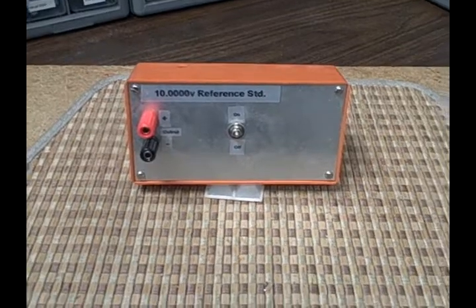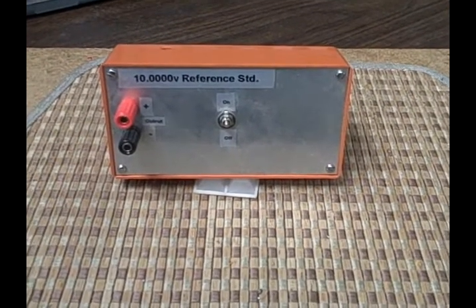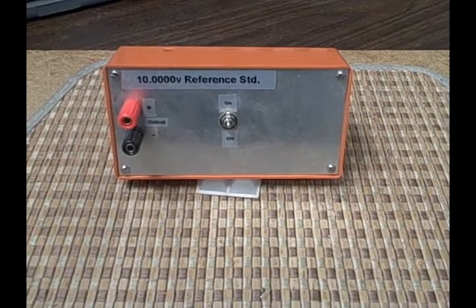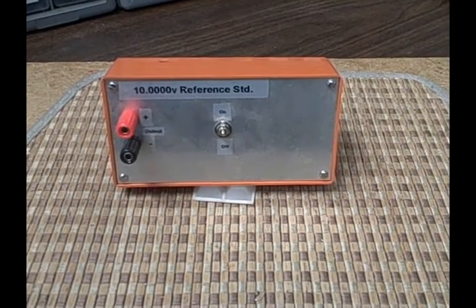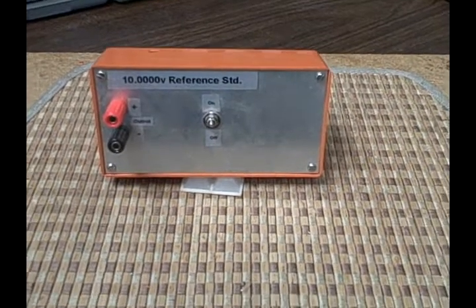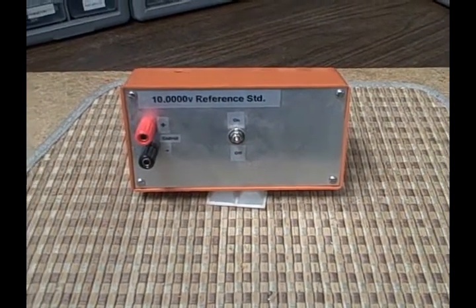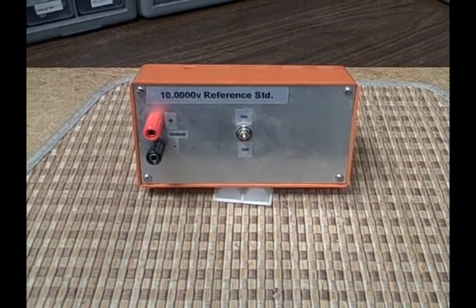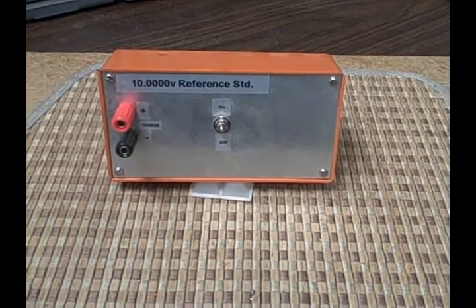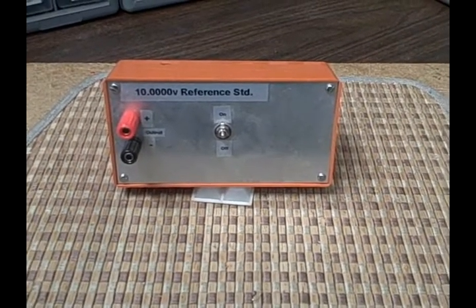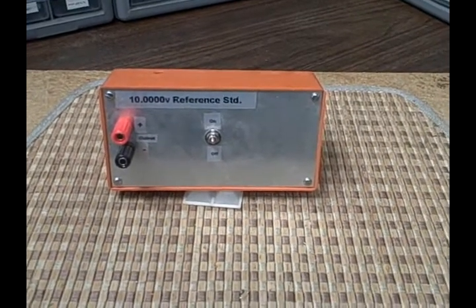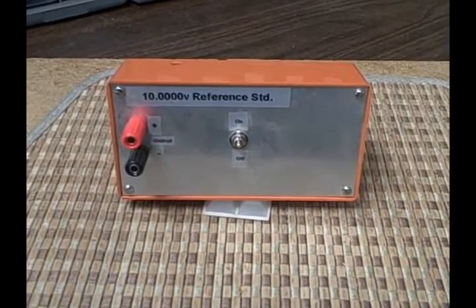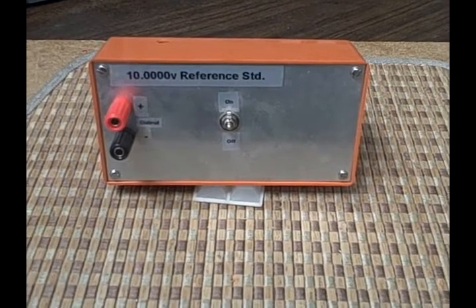A lot of times I find that I need a stable reference source that goes better than a millivolt, so in this case down to a hundred microvolts, and I use it for calibration purposes or testing. They're not that easy to come by.